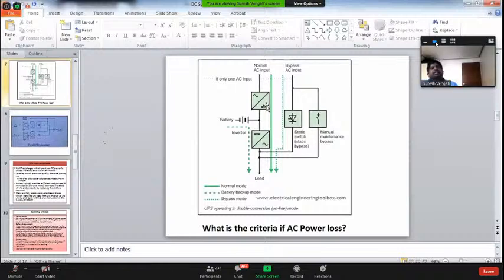Earthing is generally a very good question they ask. In industry loads we use TNS or TNC, and sometimes for IT systems also. Because it's a floating neutral, right? So when you lose the main incomer here, it goes into float mode. Through this DC you are connecting into IT mode - IT, TNC, or TNS, it's up to you and what is mentioned in the specification.